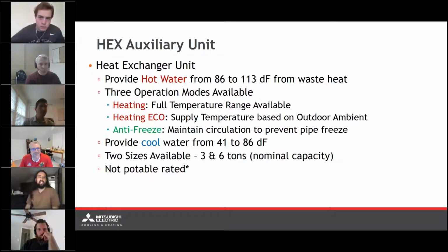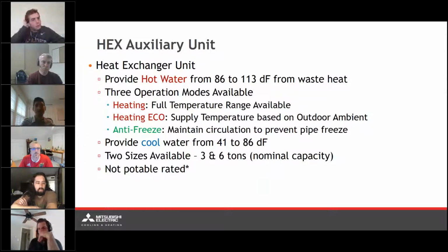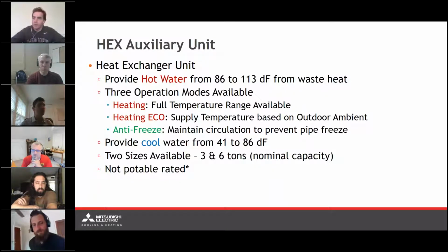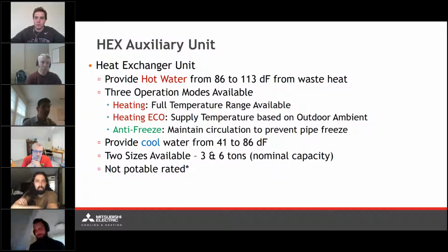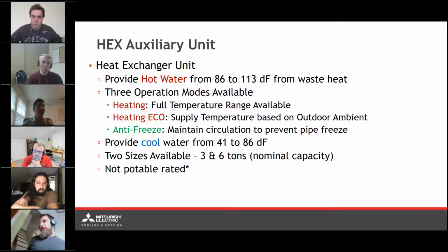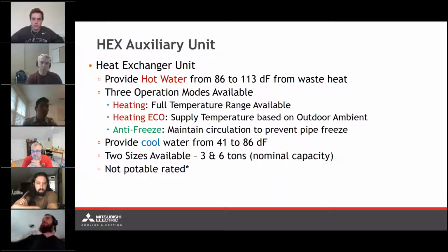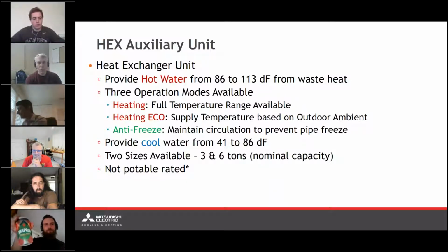So the auxiliary unit is going to have various modes of operation in heating mode. Obviously, just standard heating, where we have a full temperature range available. Heating eco-friendly mode will adjust the supply temperature based on the outdoor ambient conditions, as well as antifreeze mode, which is just going to circulate that water to make sure we're not freezing up in the pipes. With that said, we also have a reversing valve built into the auxiliary unit. Kind of same situation as a heat pump system in and of itself, where we just reverse the cycle and put out cooling rather than heating. So we're going to be removing the heat from the water as opposed to adding. In cooling mode, this is going to be able to provide cool water from 41 to 86 degrees. Again, the cooling mode is only going to be available in the HEX auxiliary unit. And the aux units are going to be available in 3 and 6 tons. Excuse me. Just take a quick water.